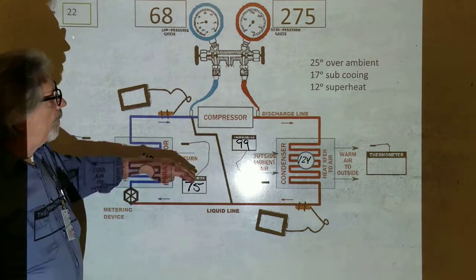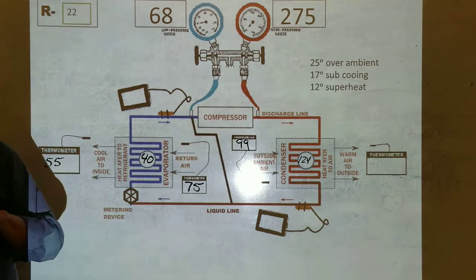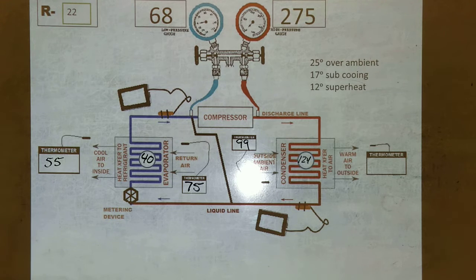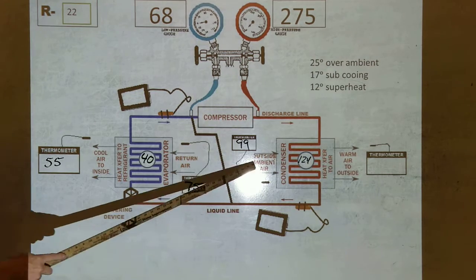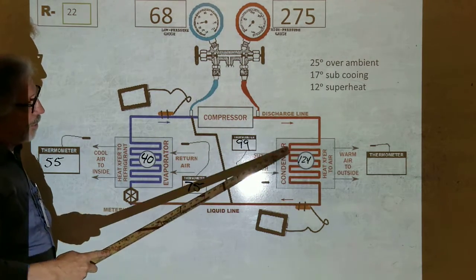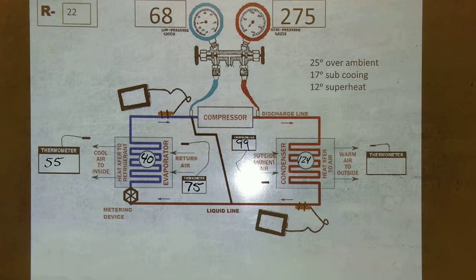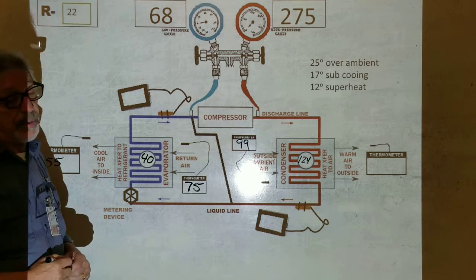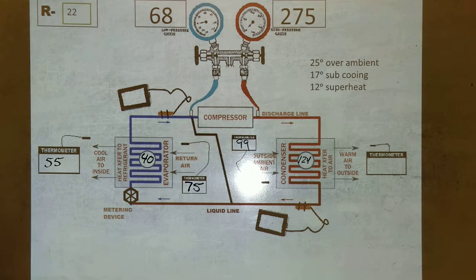Alex, you don't have to figure all that out to know what the temperature is on the outside, because you're gonna have a thermometer right there in your hand. So you'll be able to tell exactly what's supposed to go in. And you're also gonna see what your pressure and your coil temperature are, and whether or not you have subcooling. So on this, we're having 17 degrees subcooling. That's pretty good. That's good subcooling.